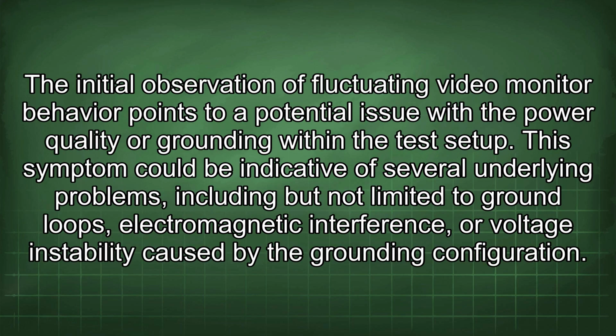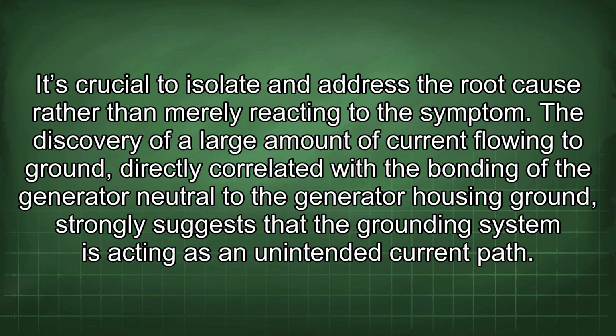The initial observation of fluctuating video monitor behavior points to a potential issue with the power quality or grounding within the test setup. This symptom could be indicative of several underlying problems, including but not limited to ground loops, electromagnetic interference, or voltage instability caused by the grounding configuration. It's crucial to isolate and address the root cause rather than merely reacting to the symptom.